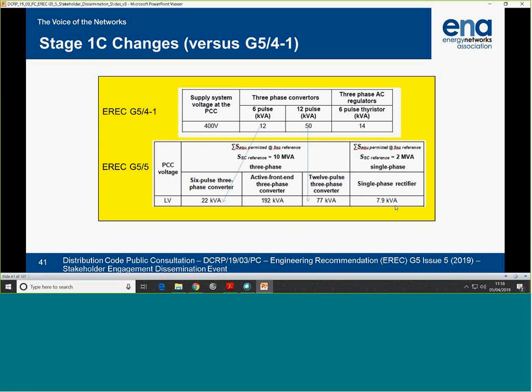So Table 6 from G5/4-1 is shown there: 6 pulse, 12 pulse, and regulators, and this is low voltage. So you could connect 12 kVA of 6 pulse converter on a, missing there is the basis, on a 10 MVA basis.